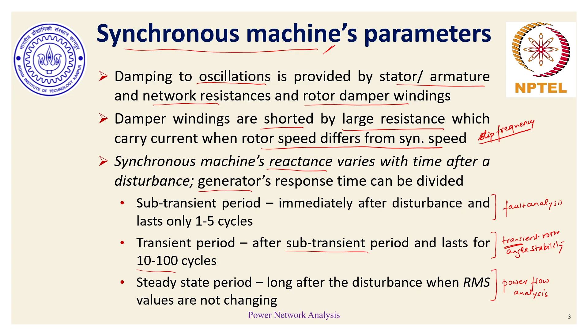So the purpose of transient rotor angle stability is to check whether, following a disturbance from some initial operating condition, the synchronous machine, be it motor or generator, can remain in synchronism. There are 4 conditions for synchronism. Voltage magnitude should match the terminal voltage of the incoming bus. Frequency should match, phase angles should match, and phase sequence should match.